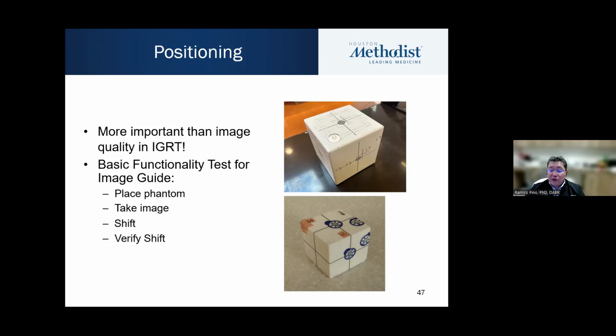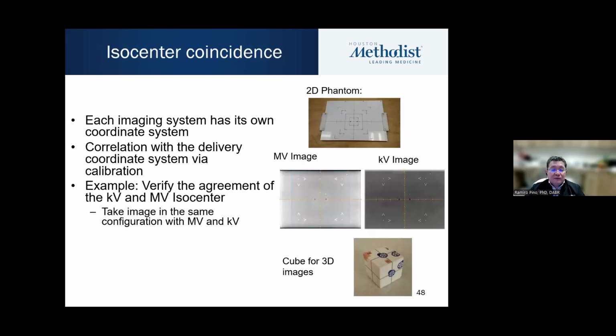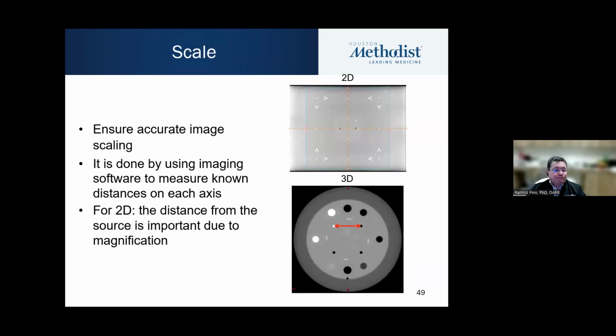These are two examples of simple phantoms that could be used for that purpose. Isocenter coincidence could also be done using those cubes, but there are some dedicated phantoms that could be used to correlate both isocenters. And the particular one that I'm showing on the right will also allow for checking scaling and dimensions. In the case of a CT scanner, you can use markers, in this particular case for a CATPHAN, that are inside the phantom itself, and verify that what you're measuring in the image is actually what you are expecting to measure.